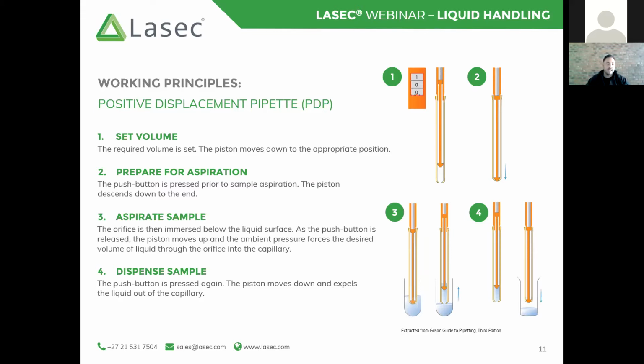So you would use it in much the same manner as an air displacement pipette by setting that volume first. With a positive displacement pipette, you will be able to physically see the piston moving up or down in that tip, depending on what volume you have set. To prepare for aspiration, you will again depress the push button. This time you can visually confirm that the piston is at the base of the tip or the tip orifice, and then aspirate. It goes without saying that it is important that your tip is sufficiently submerged in the liquid you plan to aspirate. Should it not be, you will end up aspirating air, therefore affecting your accuracy, reproducibility, as well as your precision. To dispense, you simply push down on that push button until the piston reaches the end of the tip and visually confirm that all the sample has been dispensed.